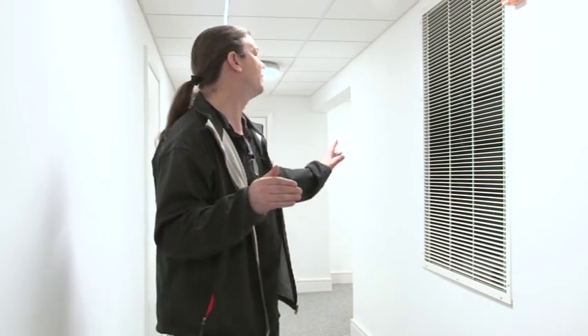Upon an activation of the fire alarm system, several things happen. One of those is that this venting system will open. The venting system will allow the smoke from that floor to be cleared to allow people clear access and egress, and allow the fire brigade services clear access and egress.